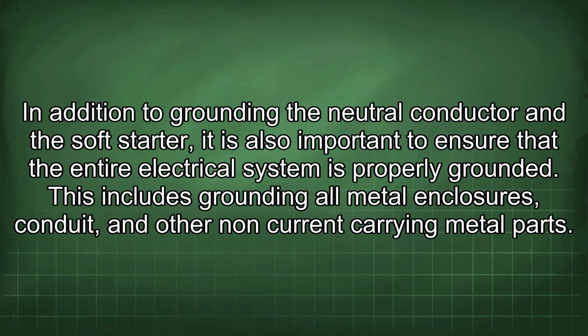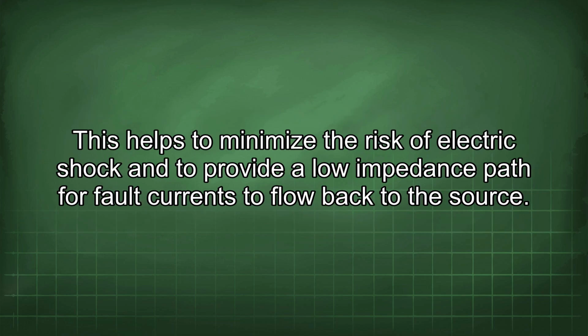In addition to grounding the neutral conductor and the soft starter, it is also important to ensure that the entire electrical system is properly grounded. This includes grounding all metal enclosures, conduit, and other non-current carrying metal parts. This helps to minimize the risk of electric shock and to provide a low impedance path for fault currents to flow back to the source.